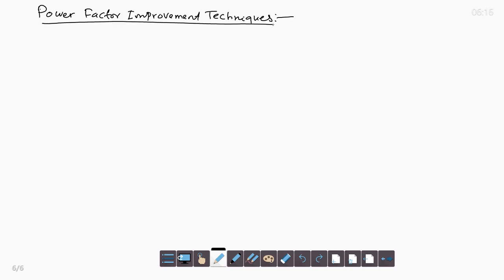From the recent discussion, we see that in a diode rectifier, voltage control is not possible, power factor is the best. In a fully controlled converter, both rectification and inversion modes are possible, but power factor is poor. In rectification mode we get forward motoring in a drive, and with inversion mode we get regenerative braking. It is an advantageous feature, but the price paid is poor power factor. In a semi converter, inverter mode is not possible, so regenerative braking is not possible, only forward motoring is possible. So how to get better power factor as well as the advantages of phase control?